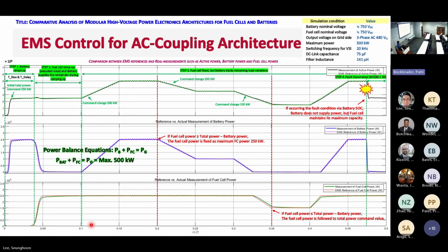Yes, so this graph illustrates how the EMS controls power sharing between the fuel cell and battery in the AC coupling architecture. In the initial phase, when the load is applied, the battery responds immediately and supplies most of the required power. The VSI limits the battery output to 250 kilowatts as the fuel cell starts from a low level and contributes very little during the initial transient. In step 2, the fuel cell begins its ramp up. Since the fuel cell has a slow dynamic response, the battery continues to supply the remaining power during this transition.